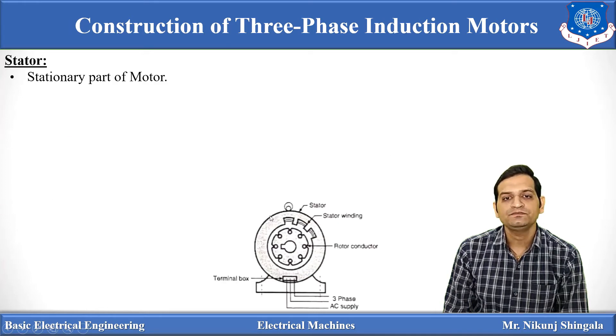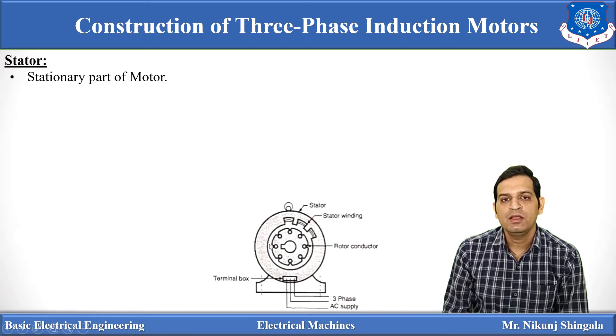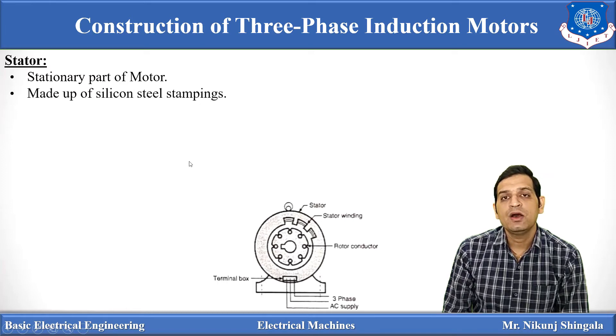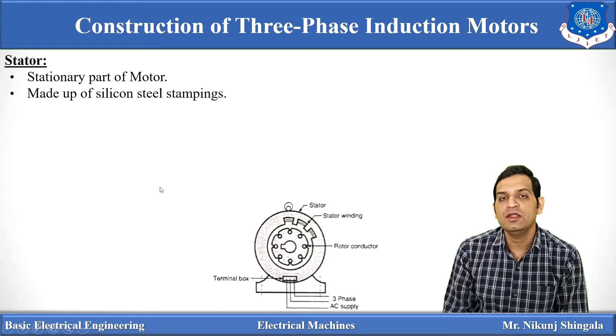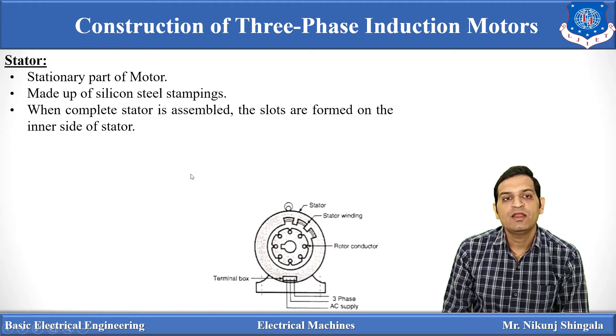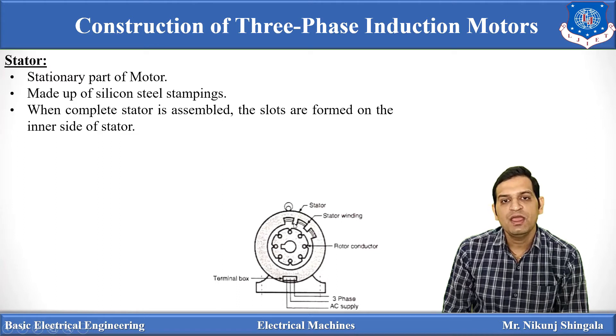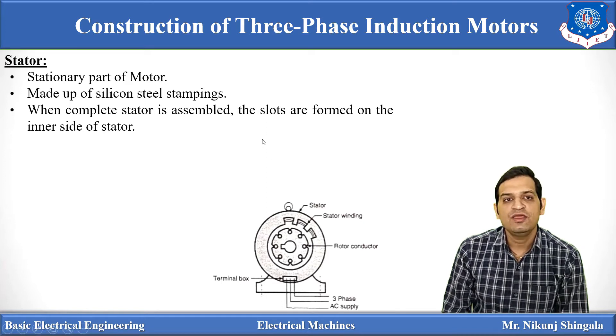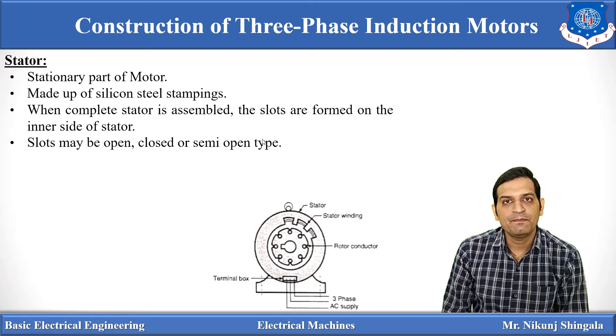Here are cut sections of the stator of the three-phase induction motor. The outer body is the frame, and the stator is the stationary part of the motor. The stator is not made up of a single piece — it is made up of silicon steel stampings, which are thin lamination sheets joined together to form the stator in a cylindrical form supported by the motor frame. When the complete stator is assembled, slots are formed on the inner periphery of the stator, and in these slots copper windings — the stator winding — are placed.